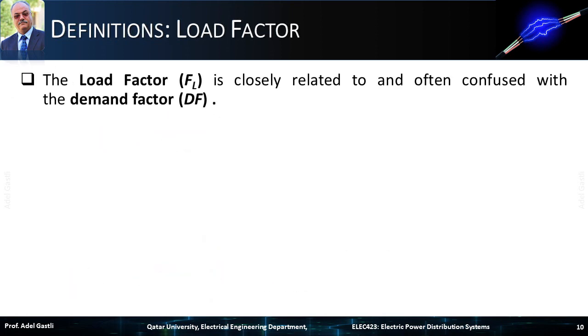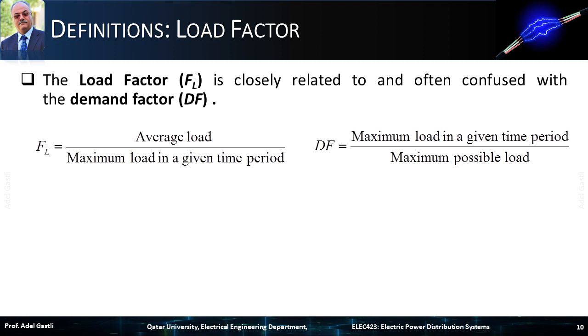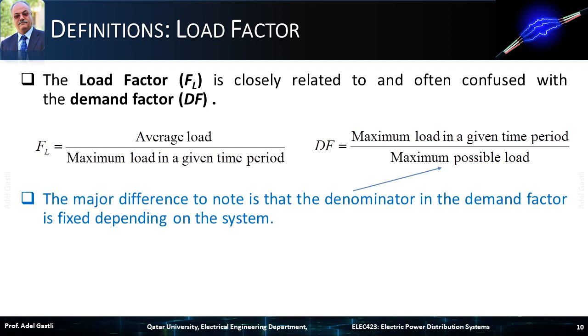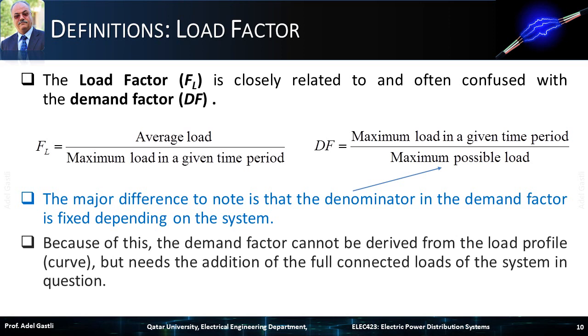The load factor is closely related to, and often confused with, the demand factor. The load factor is calculated as the ratio of the average load over the maximum load in a given time period, while the demand factor is the ratio of the maximum load in a given time period over the maximum possible load. The major difference is that the denominator in the demand factor is fixed depending on the system, so the demand factor cannot be derived from the load profile or curve, but needs the addition of the full loads of the system in question.